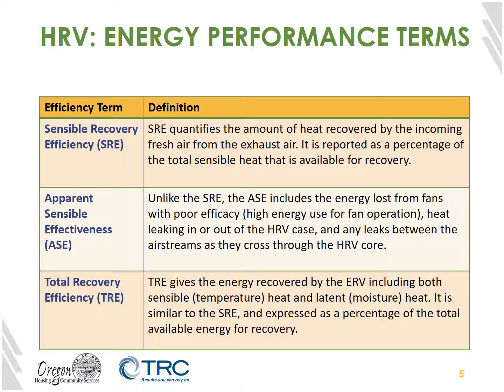Effectively, the ASE will be a ratio of how well the temperature transfers between air streams. TRE, or total recovery efficiency, gives the net energy that is recovered by the ERV, which includes the sensible heat and the latent heat, or the temperature and the moisture that is recovered. It's similar to the SRE, except that it also includes that moisture recovered from the exhaust air. For energy calculations, we typically use the SRE or TRE. For comfort, we usually talk about the ASE. Let's take a little bit closer look at why that is.